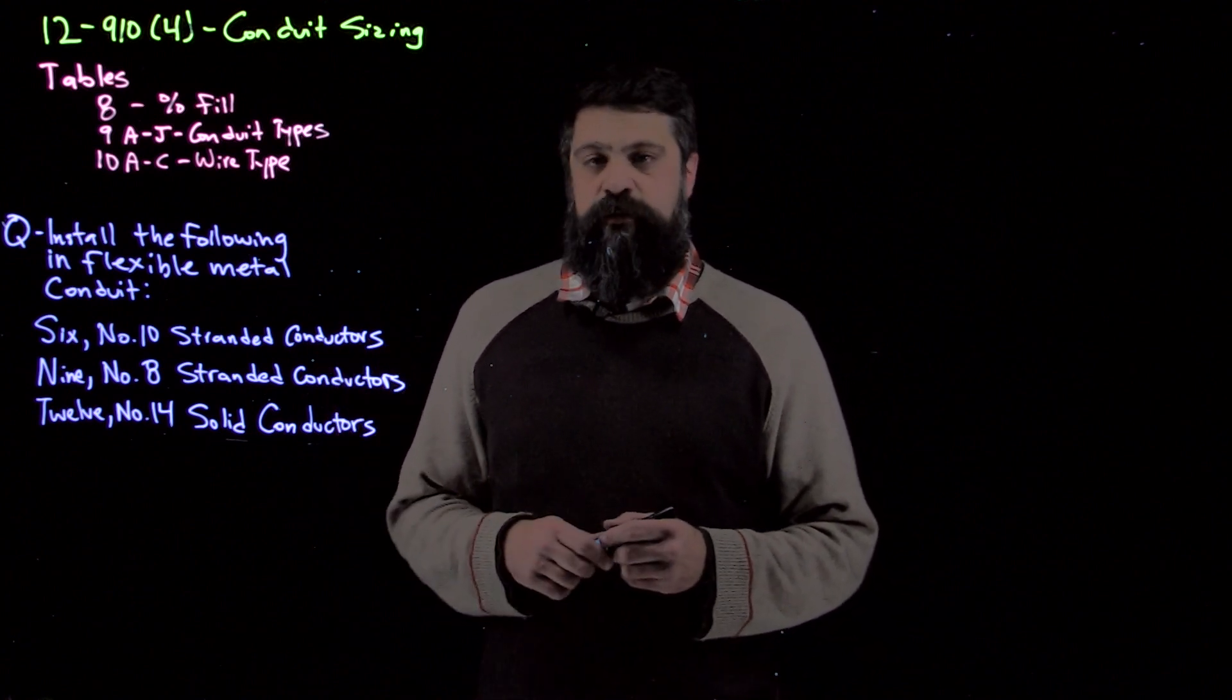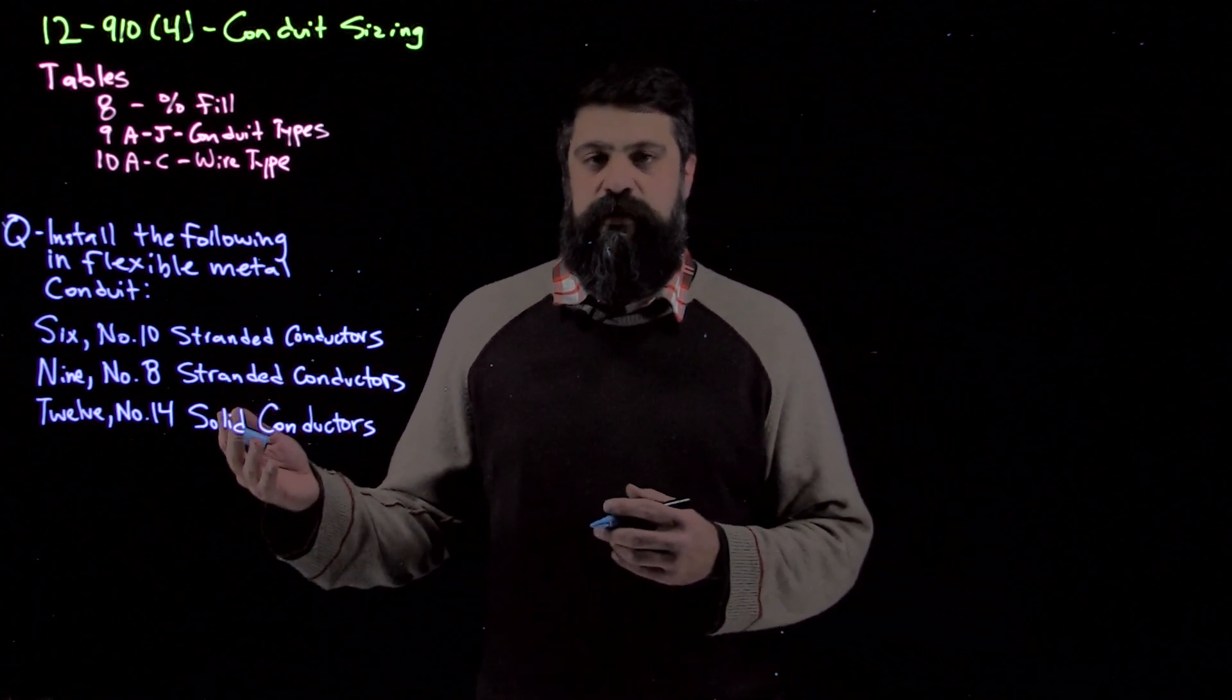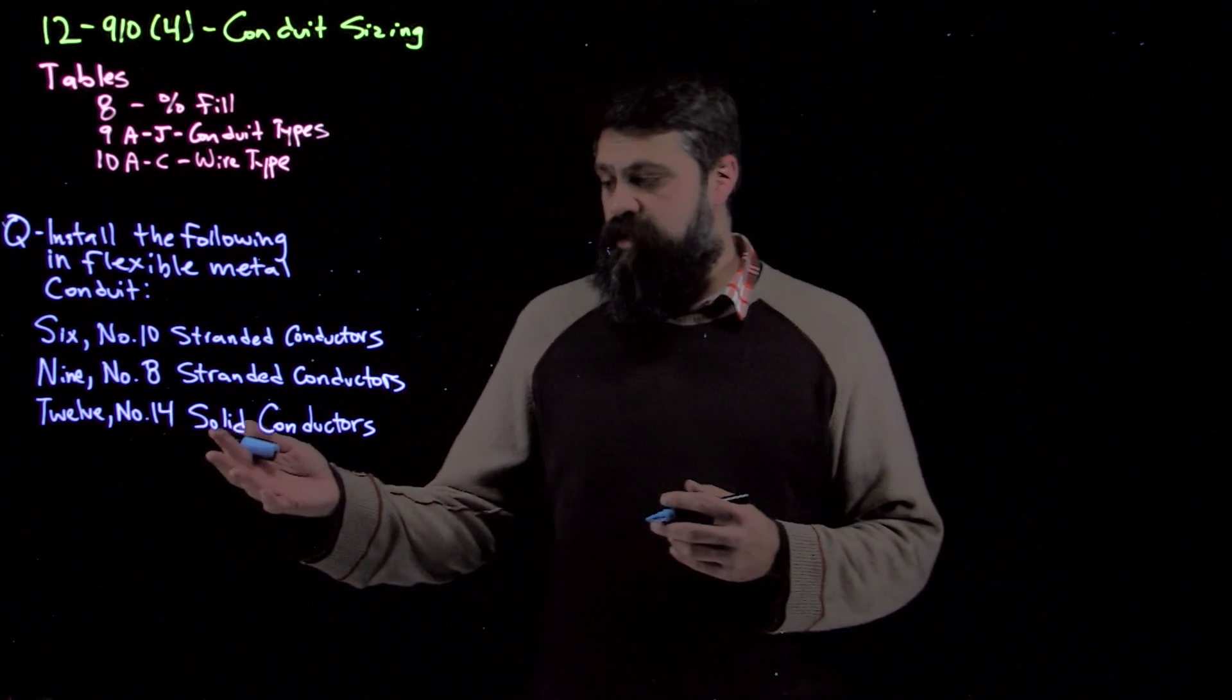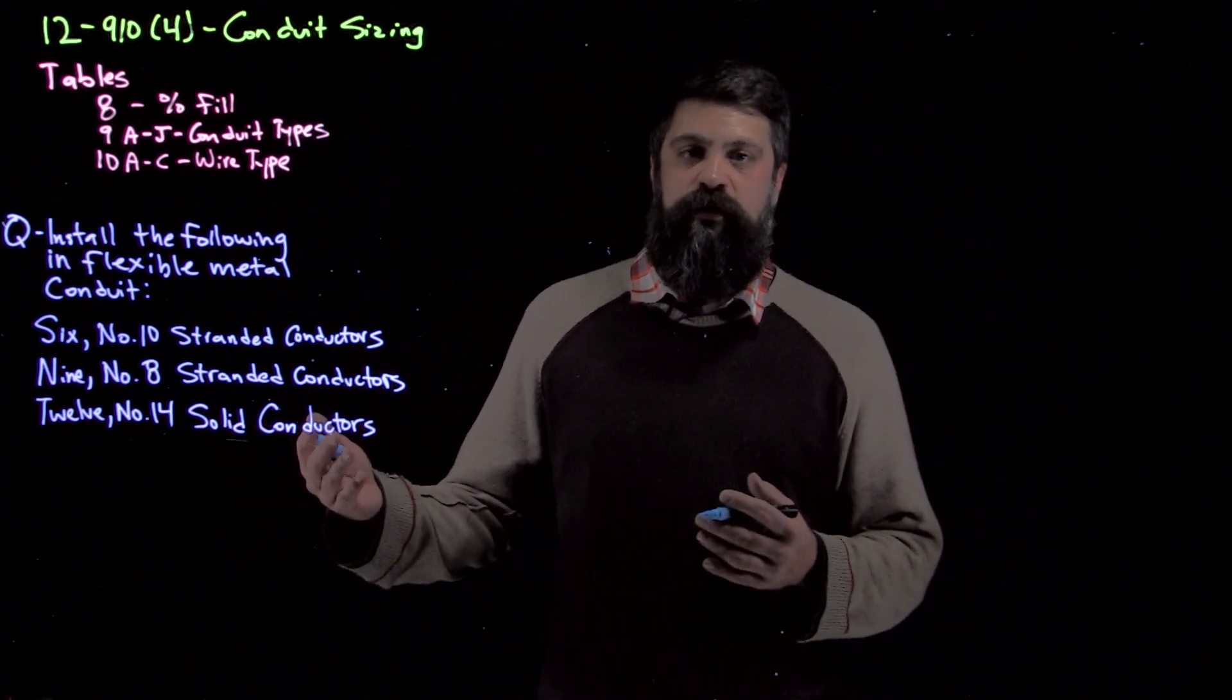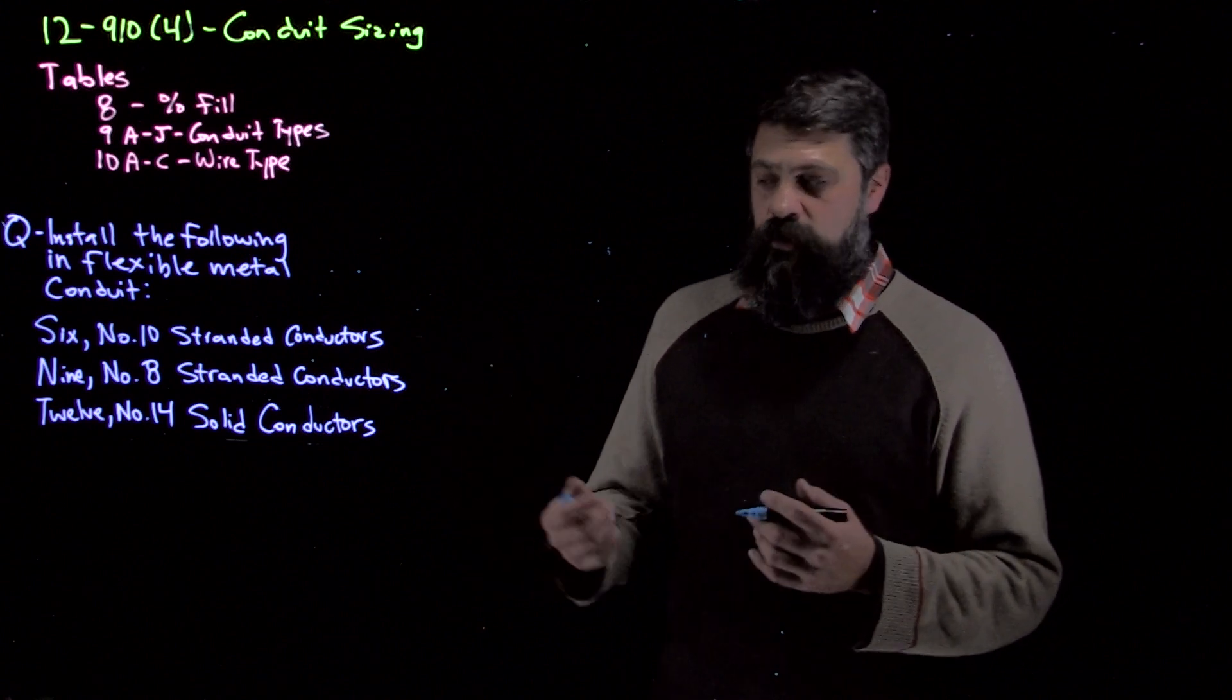The conduit we have is flexible metal conduit. So as we're going through this, not only do we have stranded, we need to know what the insulation type is on our wire as well. It's not stated in the question, so we know that we default to RW90XLPE. So as we're looking through the tables, that's the column we're going to look for.